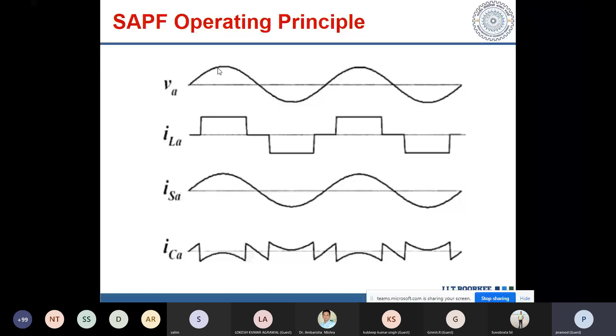If you want to reduce the rating of the active filter, you can say that only the harmonic compensation takes place, and therefore the desired source current will not be in phase with the voltage, maybe lagging by certain angle. So active power and the reactive power also comes from the source to the load. But if the source current is in phase with the voltage, it means neither the reactive power nor the harmonic power is coming from the source. The entire one is provided by the active filter, and it is used both for reactive power as well as for harmonic compensation.